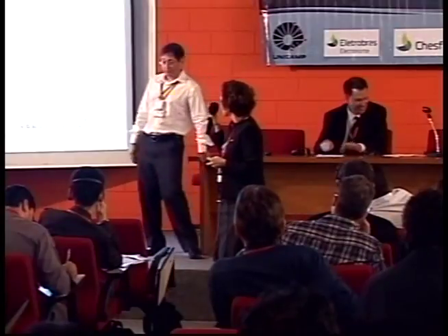From what we have seen in terms of studies without the surge arresters, we reproduced this case on RTDS using the protection that exists currently. And the protection is extremely fast, because when the fault happens in these critical regions, the current in the beginning of the line is too high. So it's almost like a terminal fault. It's instantaneous. You do not have this amount of energy. We're going to show this tomorrow.